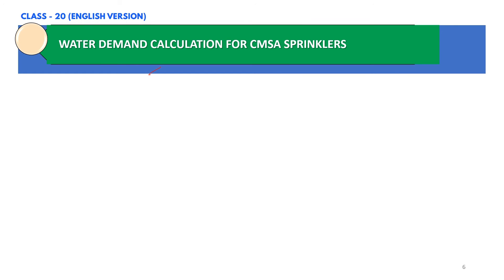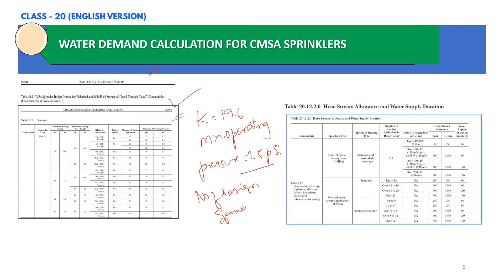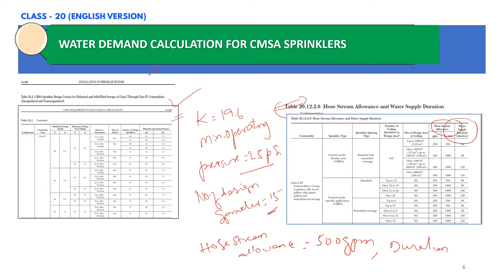In this slide, we are summarizing the data already determined. The K factor is 19.6 and the minimum operating pressure from one sprinkler is 25 PSI, both from table 22.2. The number of design sprinklers is 15. From table 20.12.2.6, the hose stream allowance for our scenario is 500 GPM and the duration is 90 minutes.